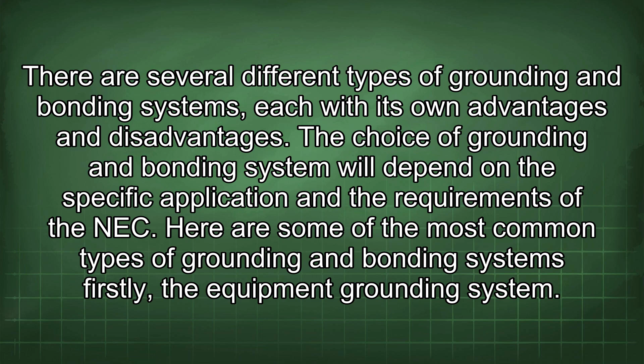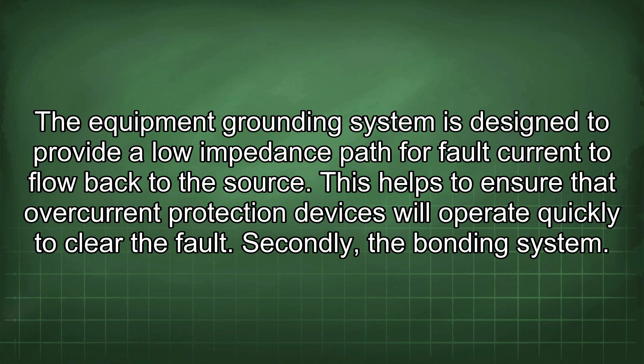Firstly, the equipment grounding system. The equipment grounding system is designed to provide a low impedance path for fault current to flow back to the source. This helps to ensure that overcurrent protection devices will operate quickly to clear the fault.